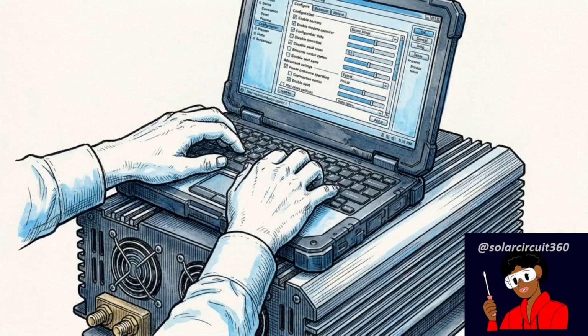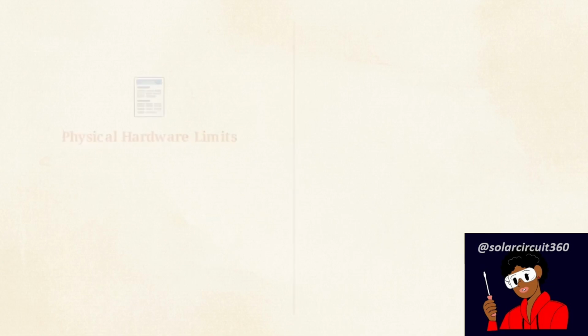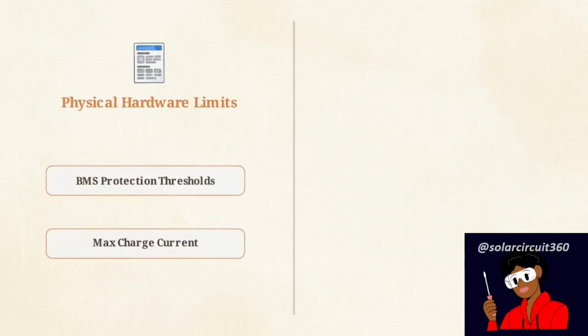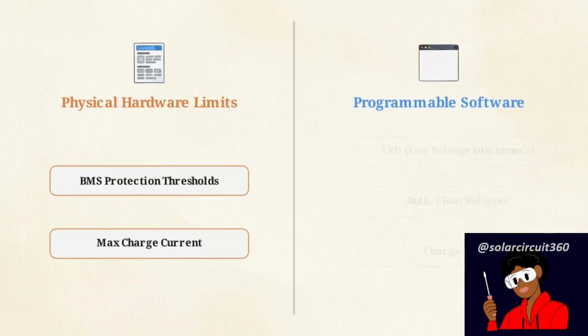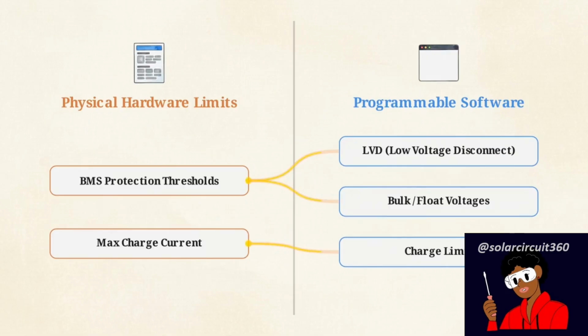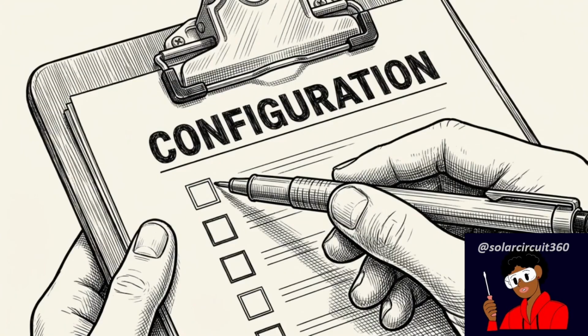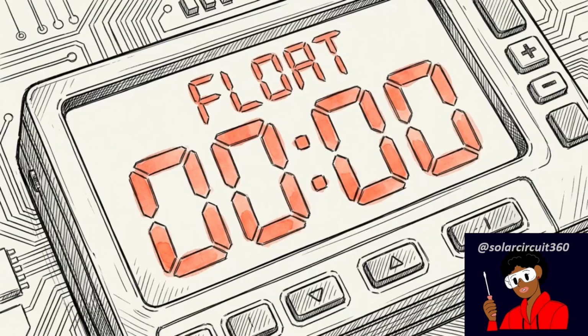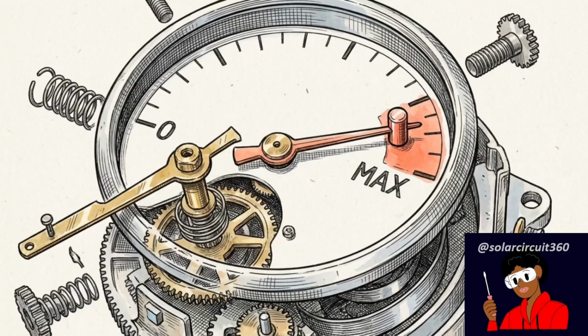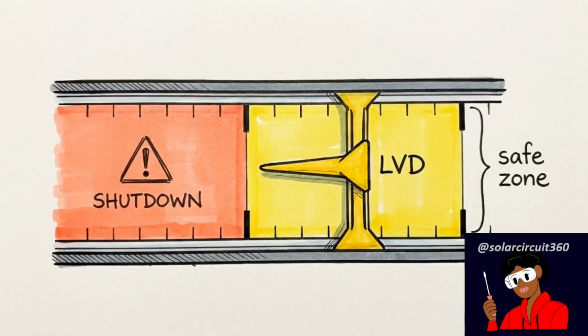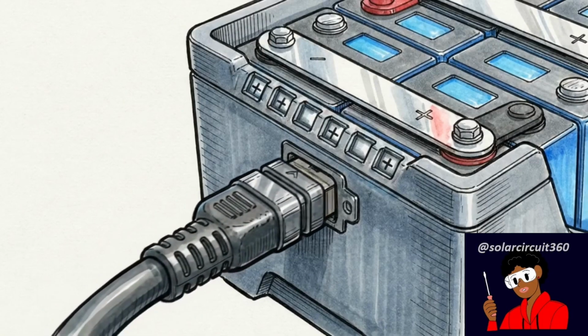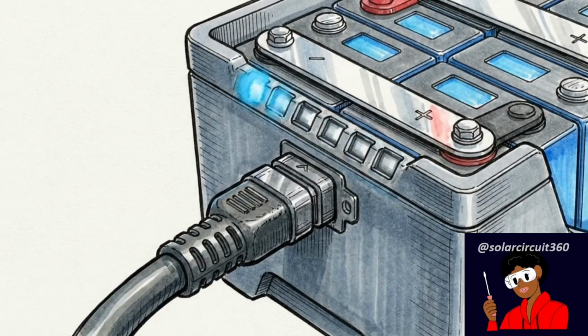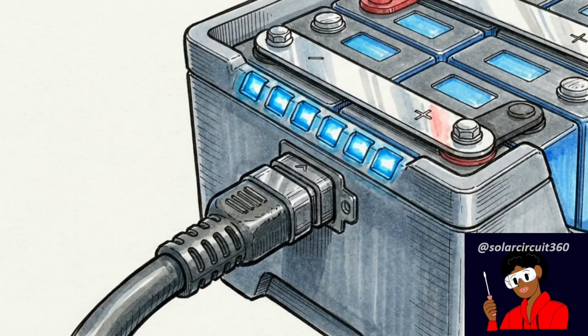Eliminating these failures requires a disciplined approach during the physical commissioning of the backup power system. The system designer must extract the hard physical limits directly from the battery manufacturer's specification sheets, rather than relying on generic lithium profiles. These static hardware limits must be explicitly matched to their programmable counterparts within the inverter's software. This requires strict adherence to a configuration checklist. Disable equalization entirely, minimize float durations, cap the maximum charge current, and properly establish the low-voltage disconnect buffer. A properly configured inverter doesn't run on standard recommendations. It runs on the exact software translation of the battery's immutable physical limits.